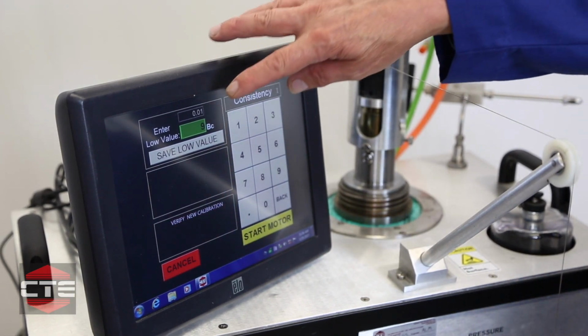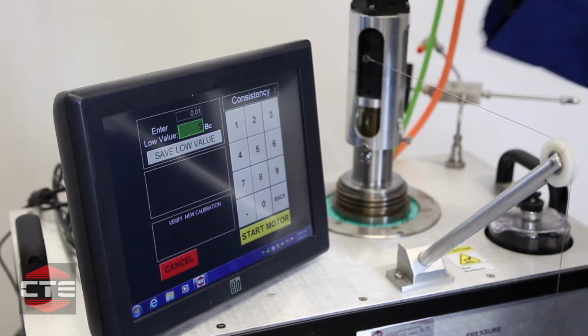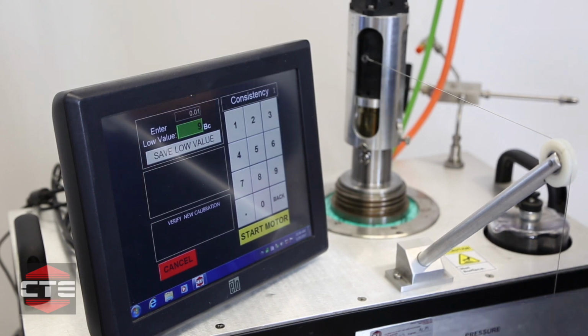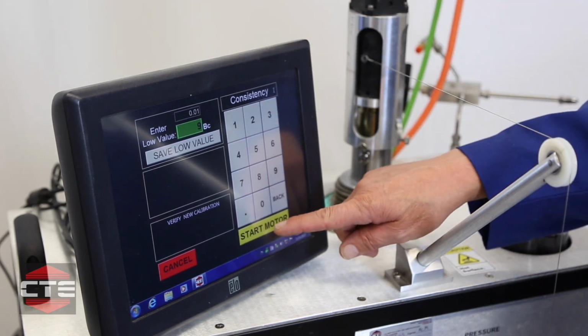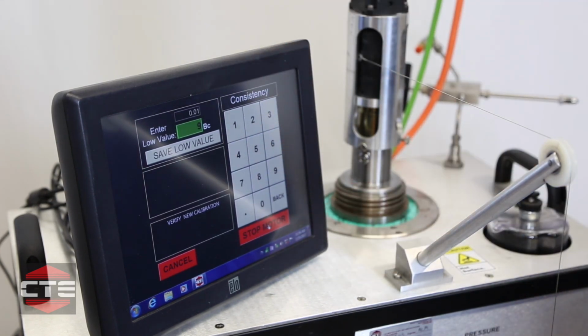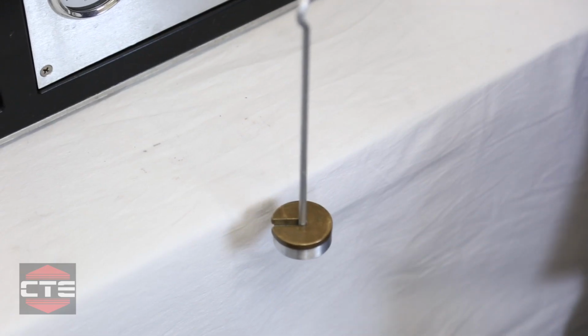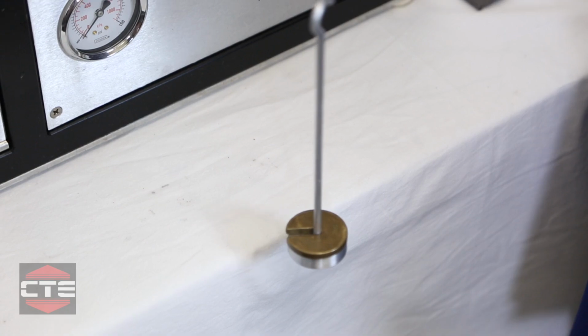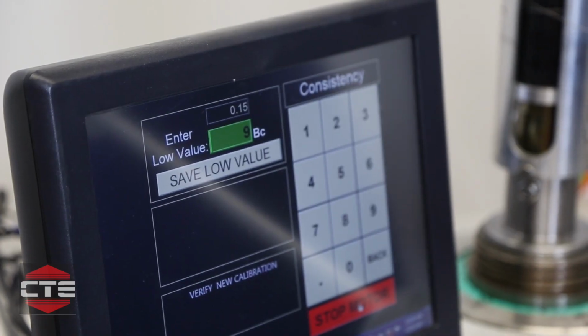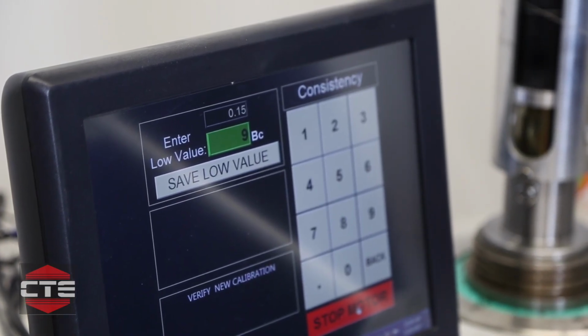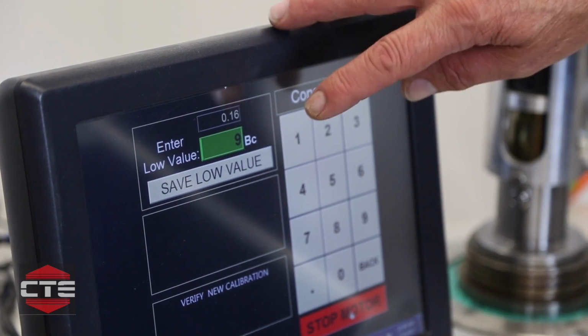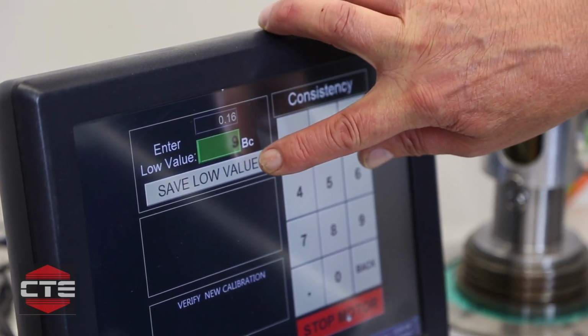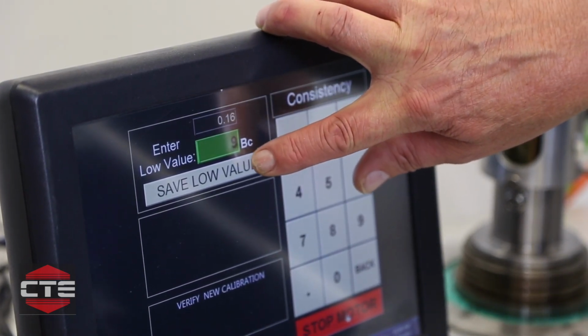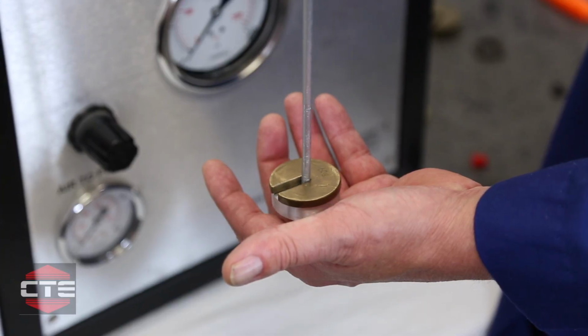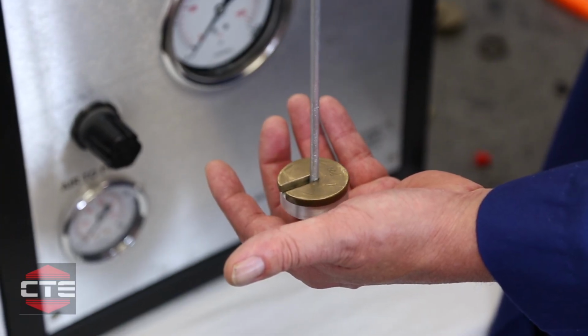This works on an average. The longer the motor turns, the more accurate the calibration. Do not enter anything you see before it makes at least one turn or one revolution, as most of those numbers will be junk. Again, what you want to look at is your raw value. When it steadies up to one number, then you know you have a good calibration. And we're going to save the low value. Get ready to support the weights, stop motor.